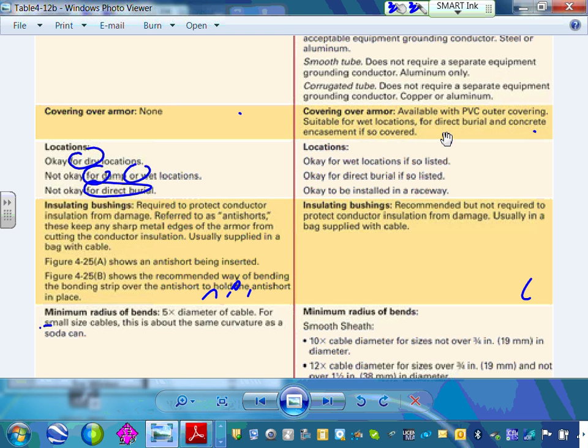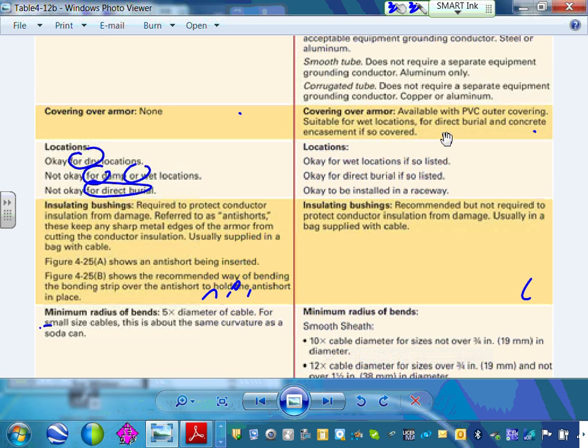Can anybody tell me the difference between wet location and direct burial? You put it outside in a wet location, it's exposed to what? The elements: heat, rain, snow, sleet. When you bury it in the ground, it's exposed to what? Water. What else? Frost. But there's something more important than that: corrosion and agents. The chemicals in the ground can act on the steel or the aluminum and destroy it.